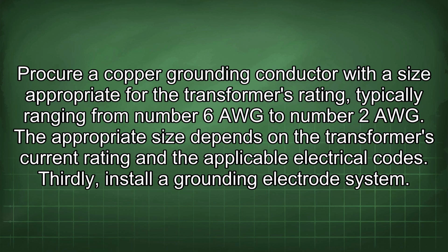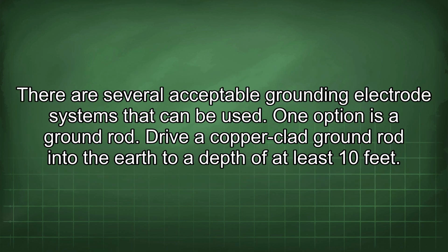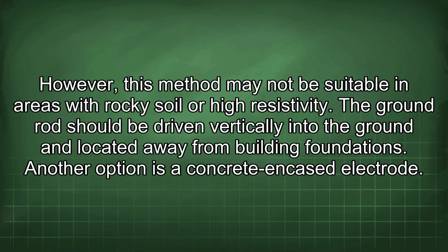Thirdly, install a grounding electrode system. There are several acceptable grounding electrode systems that can be used. One option is a ground rod. Drive a copper-clad ground rod into the earth to a depth of at least 10 feet. However, this method may not be suitable in areas with rocky soil or high resistivity. The ground rod should be driven vertically into the ground and located away from building foundations.